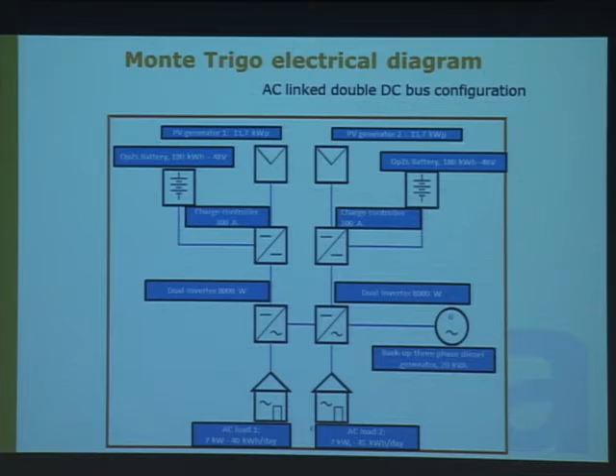The electrical configuration is, in reality, an AC-linked double DC bus, because the battery had to be so big that it's split into 2 DC buses. The inverters can act as master-slave, so you can take a bit more power from one side than the other.